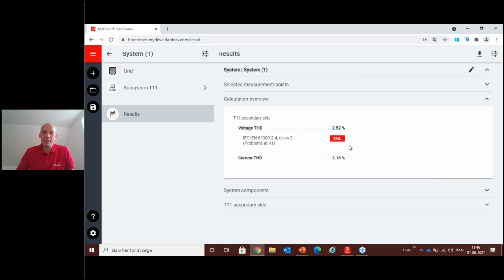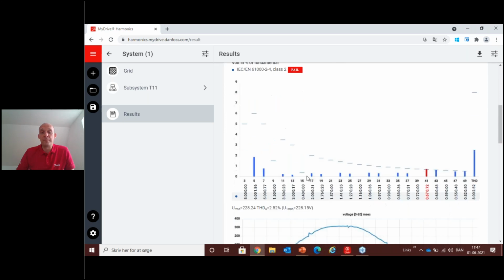So actually, this is quite an interesting example. Now you can see the voltage distortion went down to 2.5%, and the current distortion went down significantly, to 2.13%. But you can also see that we're actually not compliant with the standard anymore. So you have added mitigation equipment, but it has not made the situation better. On the contrary, it has made it worse. The reason is that the low harmonic drive impacts the higher order harmonics. Everything is clean down in the lower end, but you start generating more noise in the higher end of the spectrum.